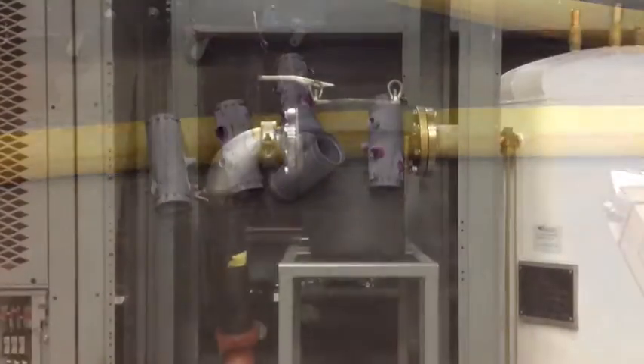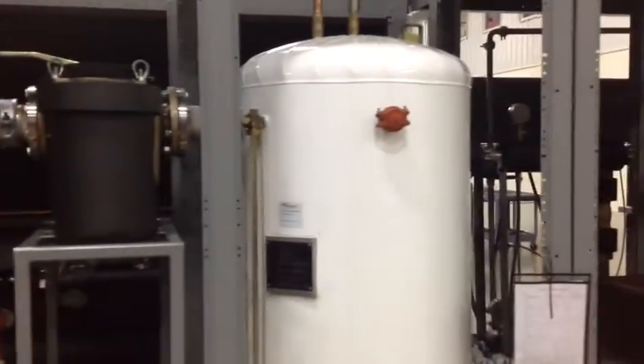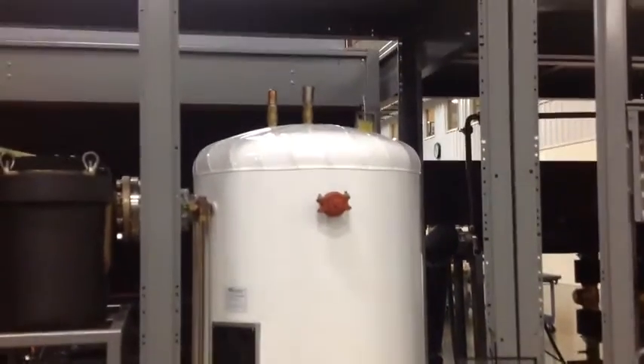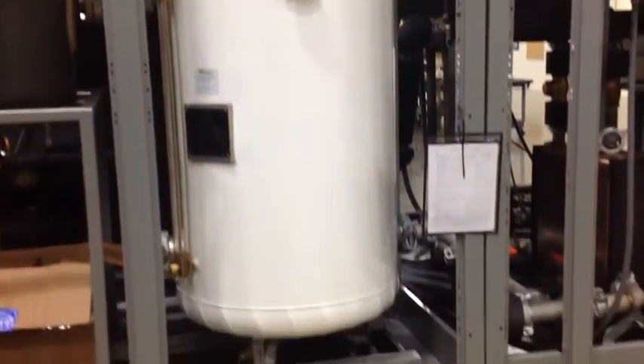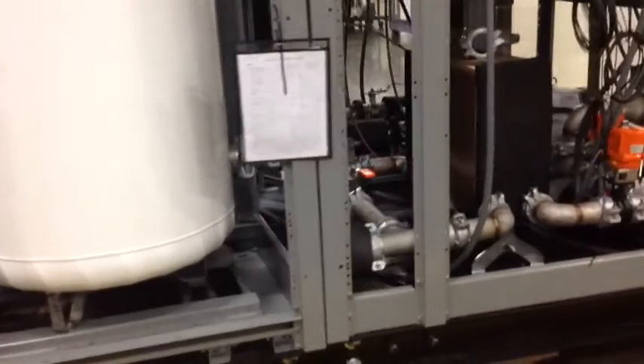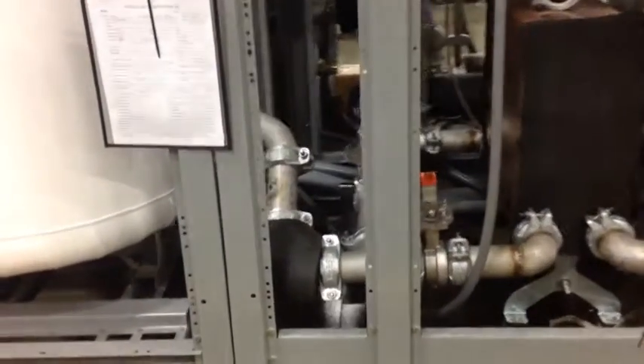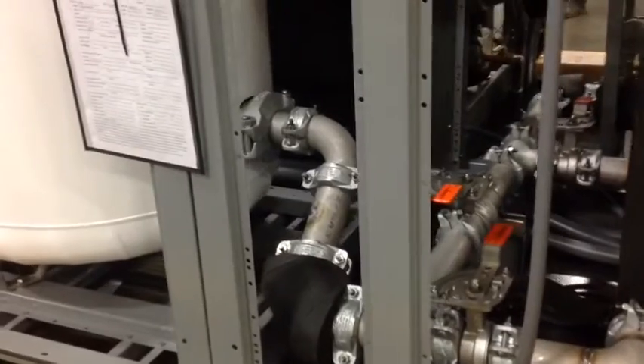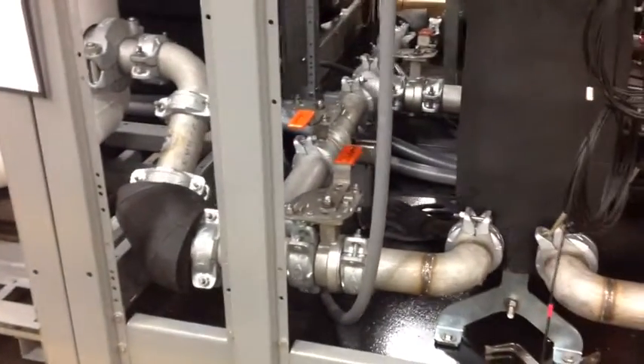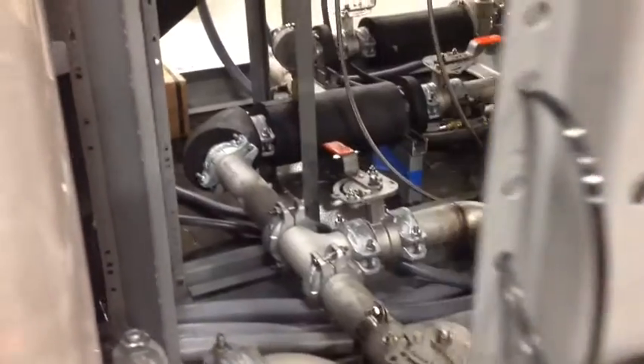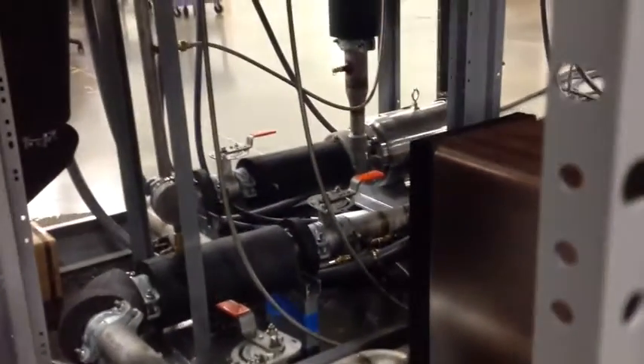These are stub pieces that are shipping loose with probes for thermometers, pressure gauges, and sensors. This is the 160-gallon storage tank with the bypass connection. Water comes in through the tank, out of the bottom of the tank, and then over into the pump suction. The normal path is for water to go through the heat exchanger, but you can see there's also a set of isolation valves to isolate the heat exchanger and open a bypass path. You can see the primary and backup pump in their stainless steel housings in the background.